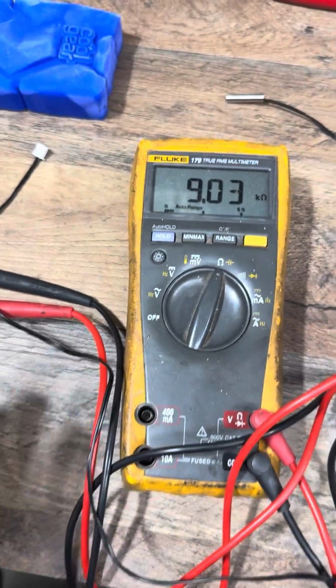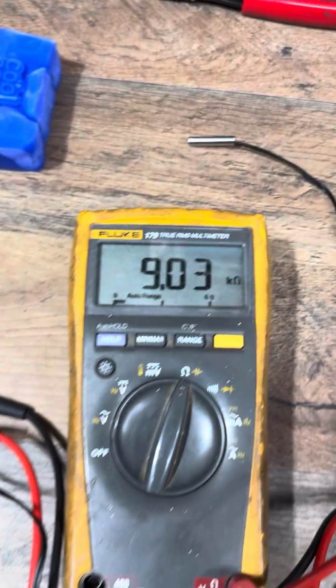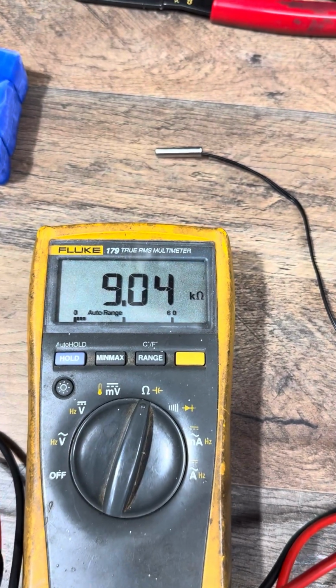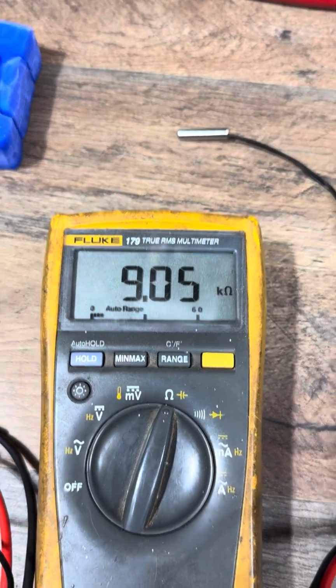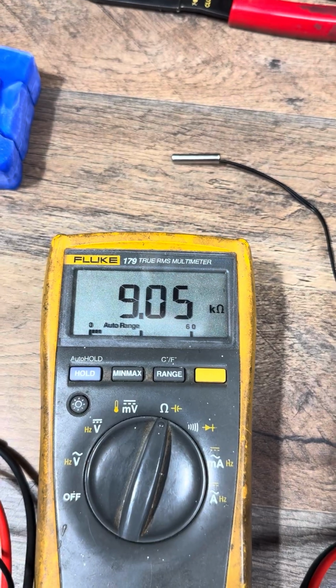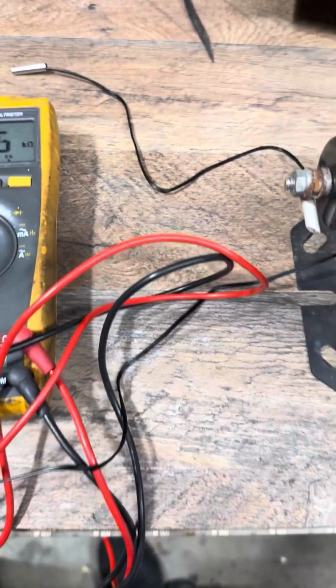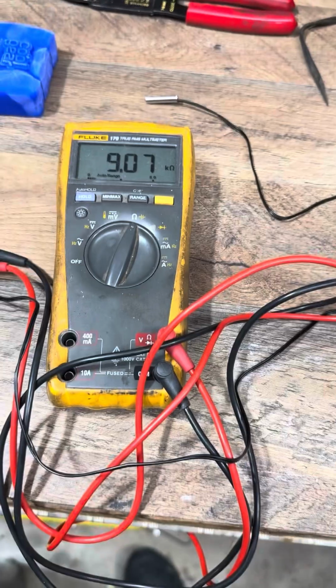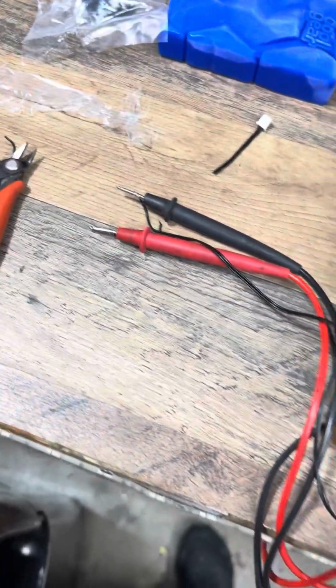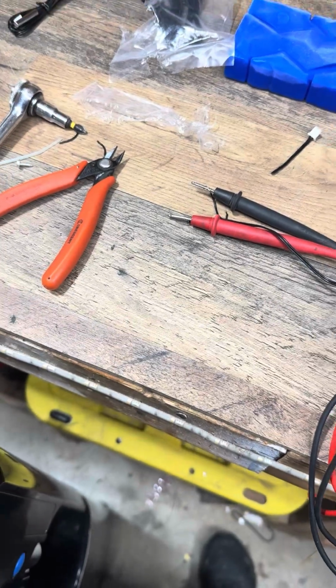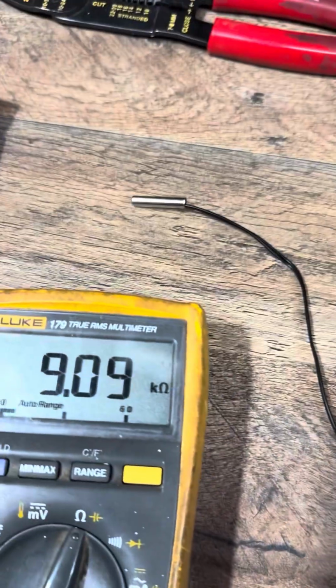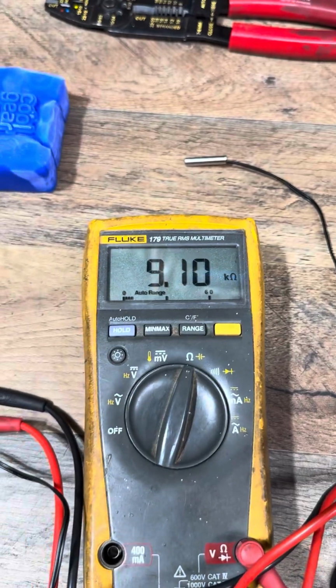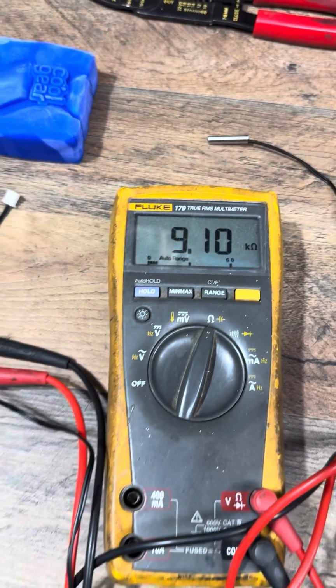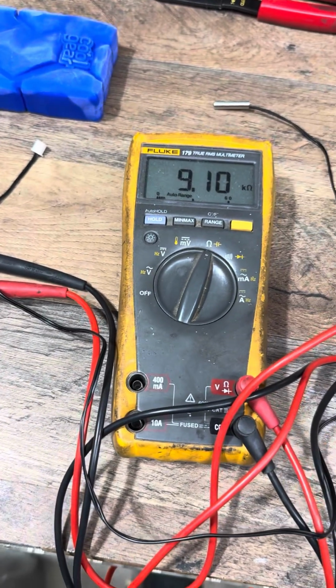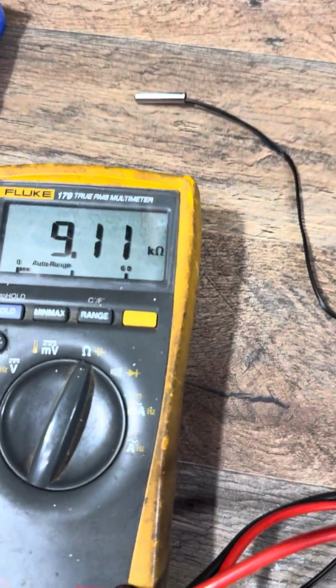Okay guys, so what exactly is the temperature probe? So basically it's a device that senses the temperature of an object, and it changes its characteristics based on that temperature. It'll feed that information, typically a resistance, to the control board inside your unit. With the varying and changing resistance, your controller board responds accordingly. So when this little guy malfunctions, it can send erroneous information to your controller, and thus create the problems that I think we're having here today.